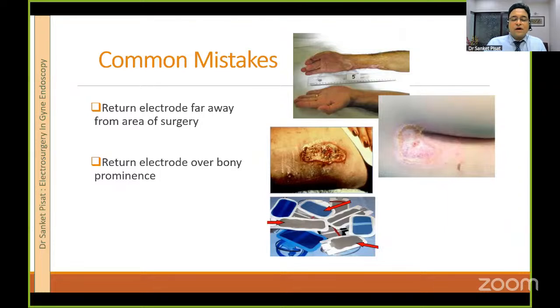Instead of that, even today I see at many places where I go to do visiting surgeries, return electrodes are applied over bony prominences like the shin of the tibia, or over the forearm where it is just under the proximity of the bone. What will happen is that the current will directly exit from the skin over the bony prominence and go into the bone, thereby creating a minimal area of contact and thereby creating a return electrode burn.